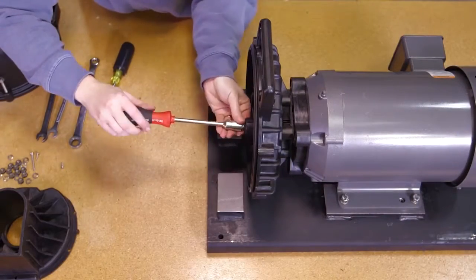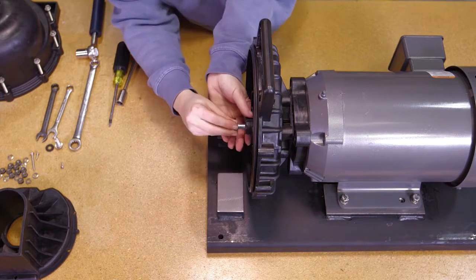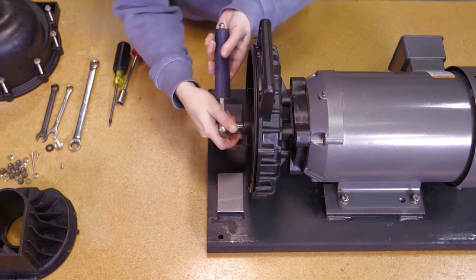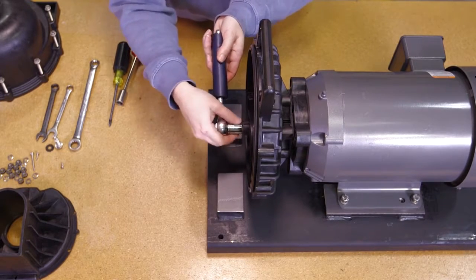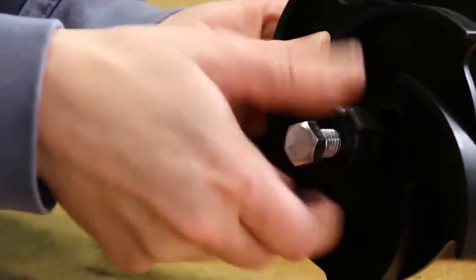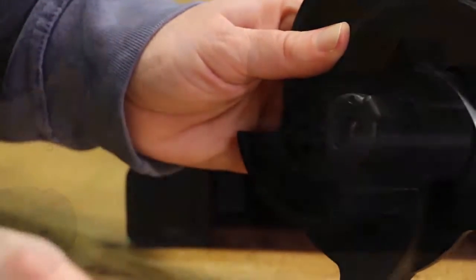Remove the impeller bolt and gasket from the impeller. Screw a 7/16-14 hex head cap screw into the impeller snout. As the bolt is tightened, the impeller will be pried off of the shaft of the drive unit. Remove the 7/16-14 screw once the impeller has been removed from the drive unit.